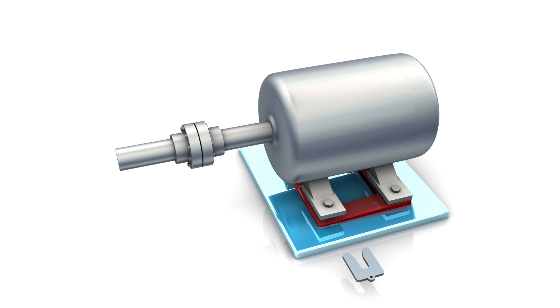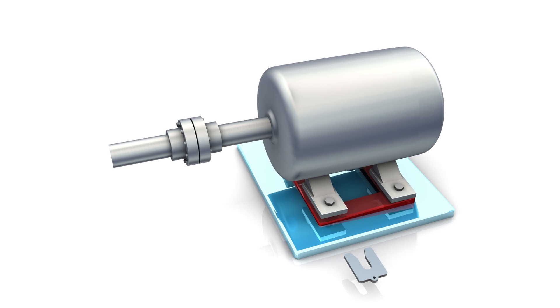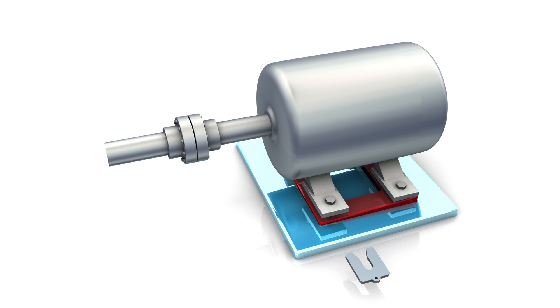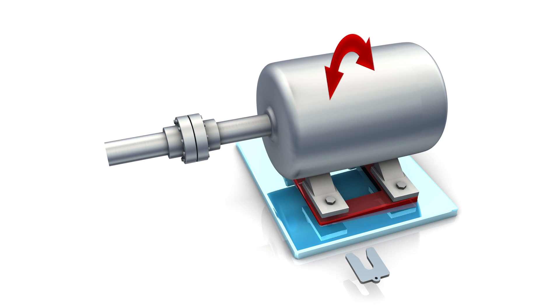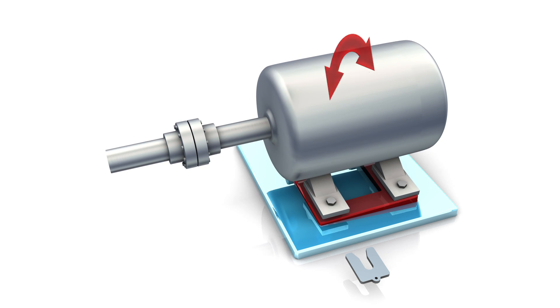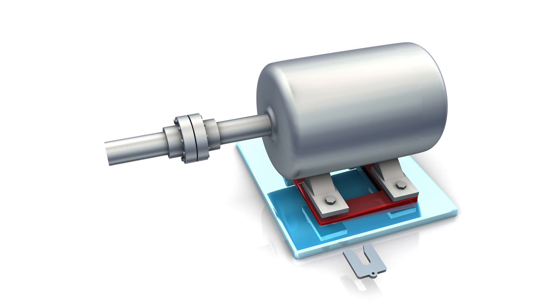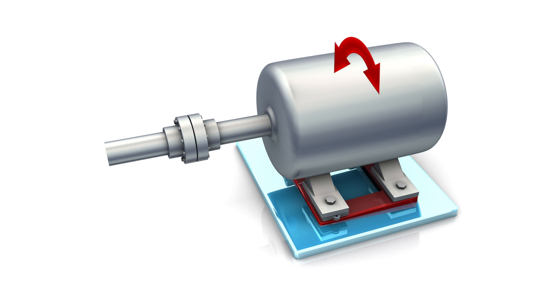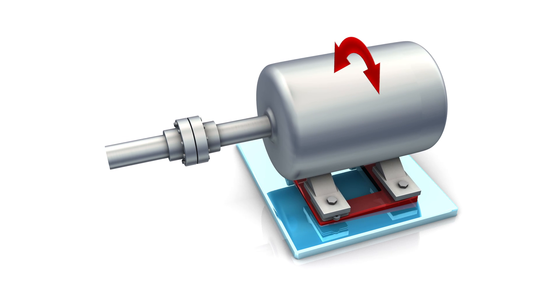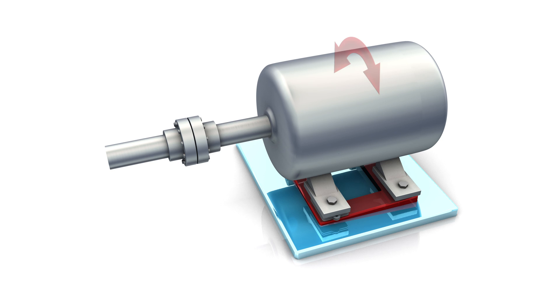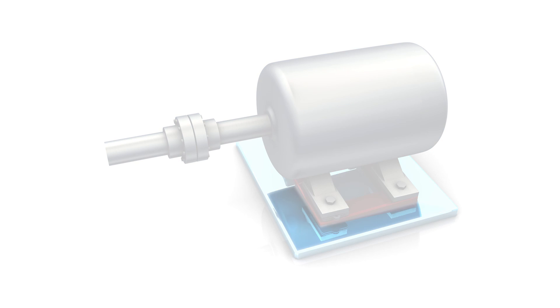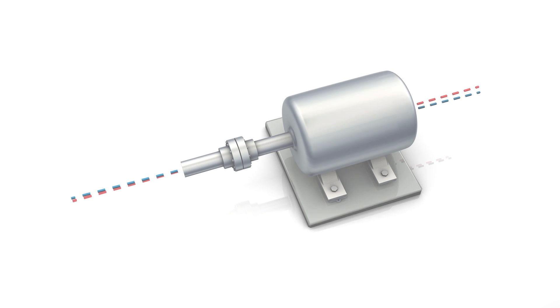Soft foot describes faulty seating of a machine frame that results in a wobble or misalignment of machine parts. Mitigating soft foot conditions by propping up one leg can unbalance the other legs and exaggerate alignment problems.